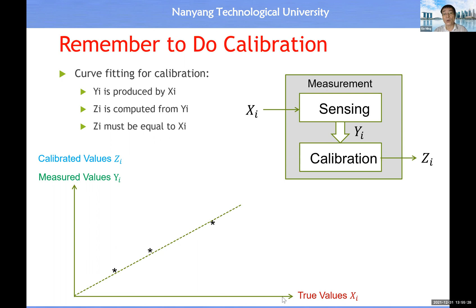Also after calibration, try to do experiments in order to come up with these indicators related to error analysis, because the user or buyer of your product or system may want to know these values. This is why it is important to do error analysis in order to come up with the values for systematic error, repeatability error, accuracy, and hysteresis error. You must do this error analysis, because the buyer or user of your sensor or measurement and sensing system needs to know these values.